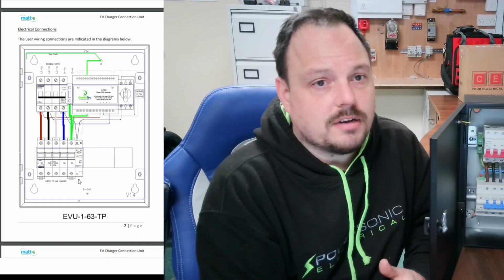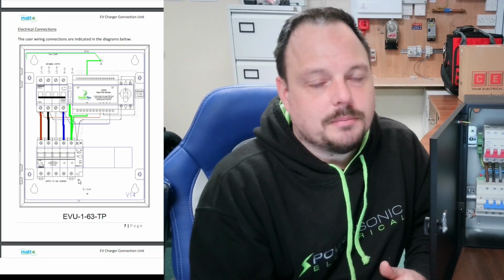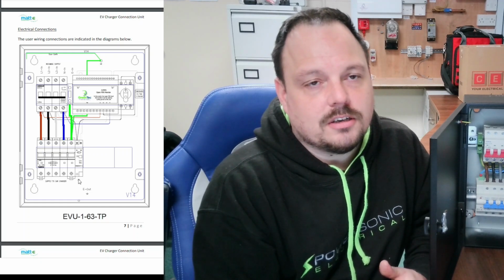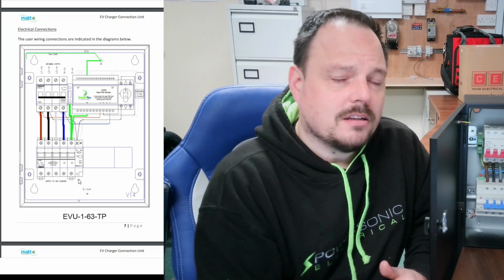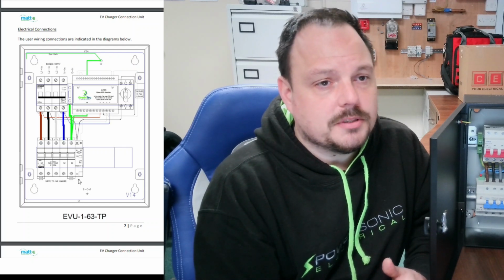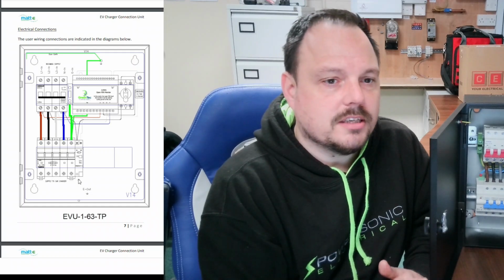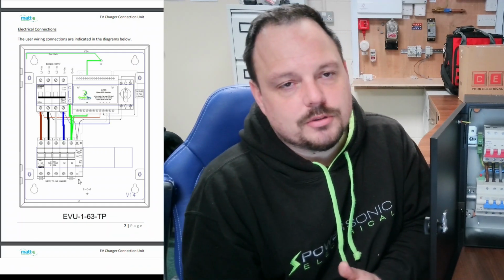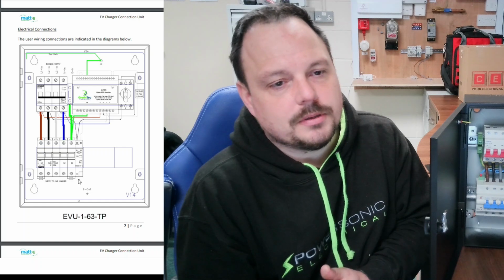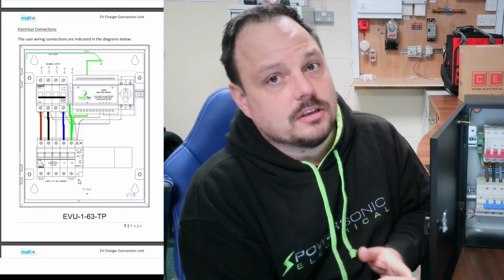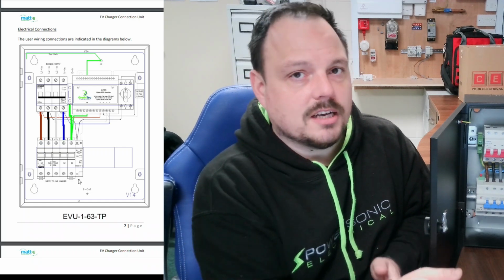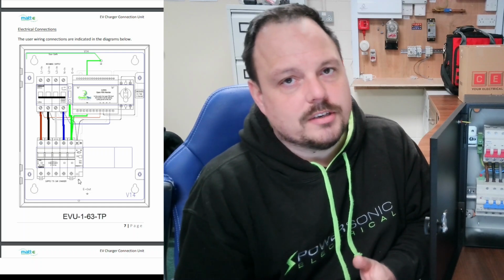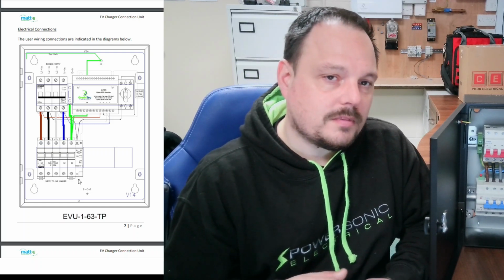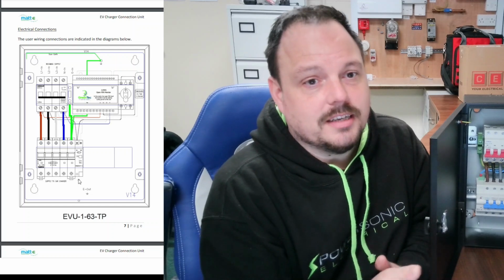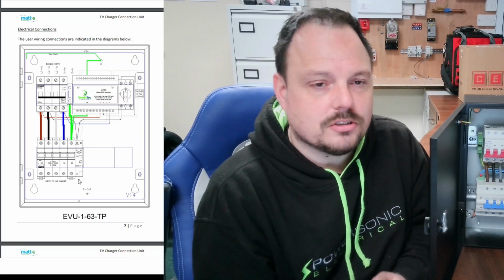So if the earth is rising on any of the bonding in the building or anything like that, you've still got all of the armoring and any glands rising and falling to the same potential internal to that installation. If we have them connected through to the charge point, for example, and there's no physical connection onto the Matt-E product and essentially the internal earthing system, you can then have an issue if you've got a fault external to that being imported into the earthing system as a whole. So I prefer to do it like that.